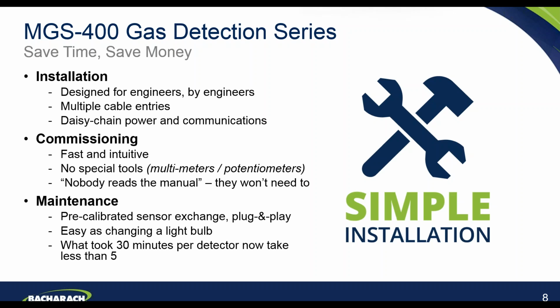From a commissioning perspective, the product should be fast and intuitive. There should be no special tools required, as is the case now with the MGS-400 series. So in terms of the commissioning, you don't need to utilize any multimeters. There are no potentiometers to adjust. And ultimately, one of the key feedback points that we had from our customer base was that not many people read the manual, and that's probably true. With the MGS-400 series, it's been designed that, quite frankly, you don't need to read the manual. It's extremely intuitive and simple to use.